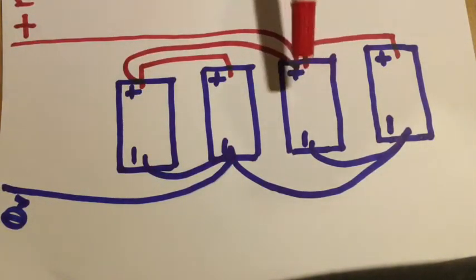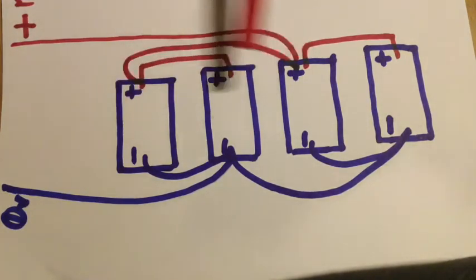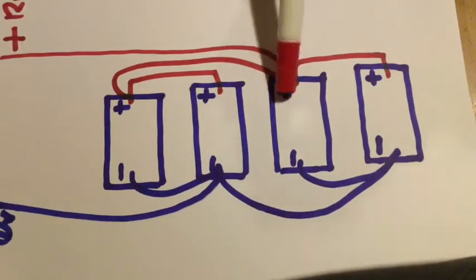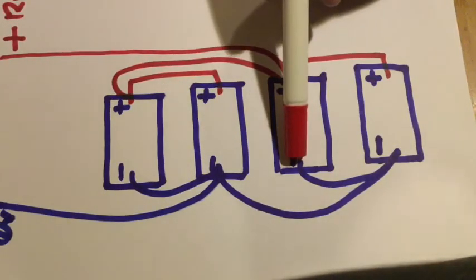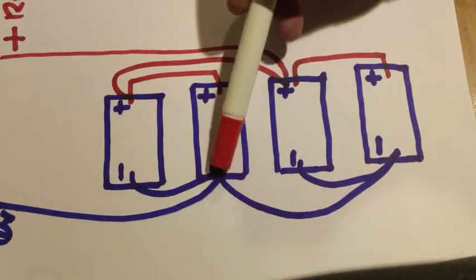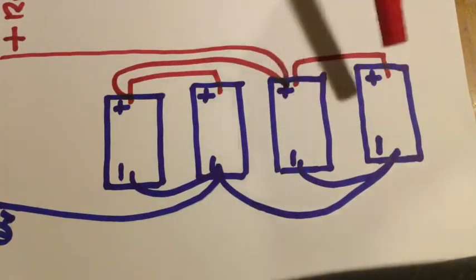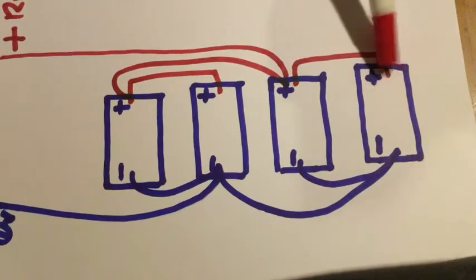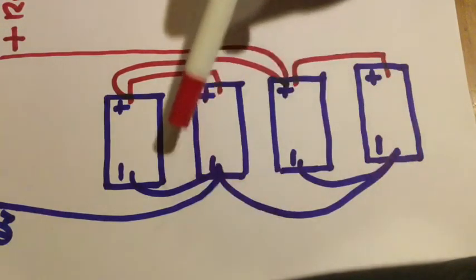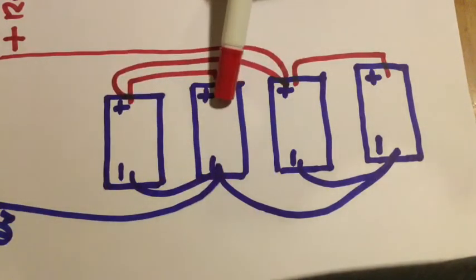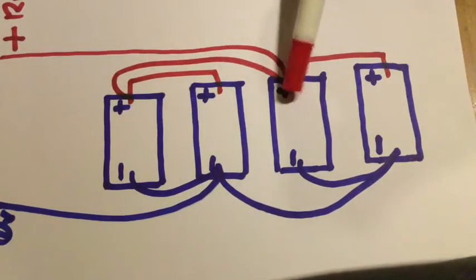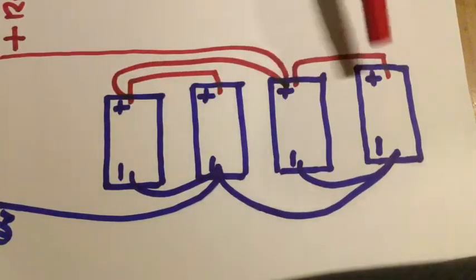This one here, the positive's connected directly, so the negative goes through one short and one long, same resistance. And if you look at the drawing, it's the same for all the batteries, one short, one long. They're all balanced equally, they'll all charge at the same rate.